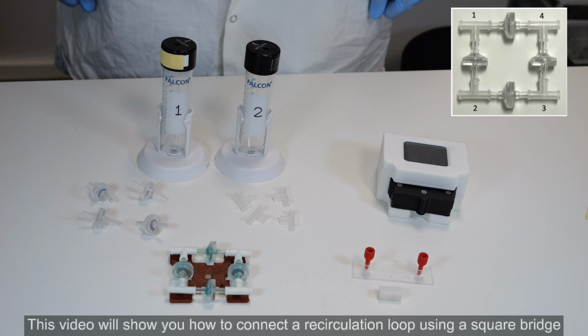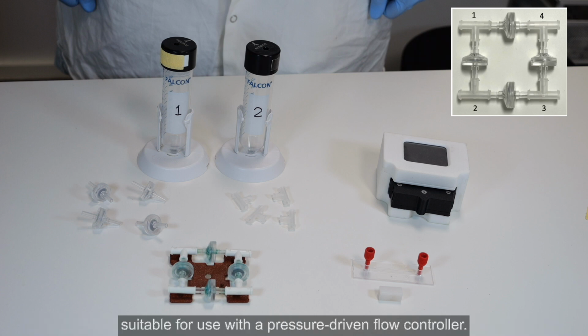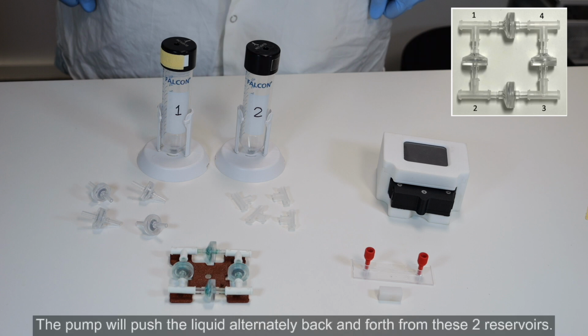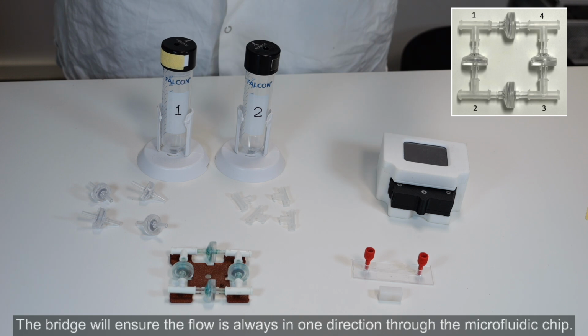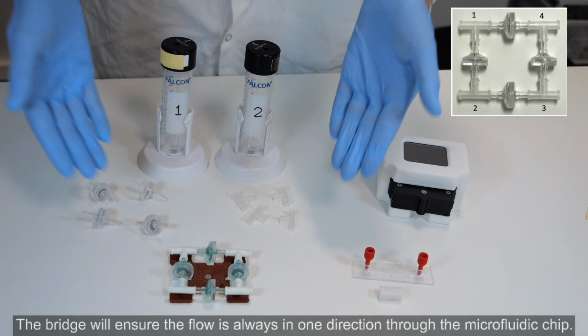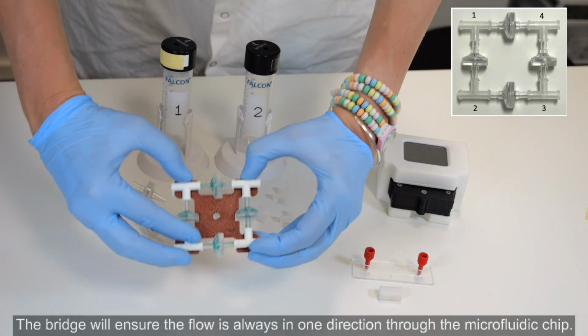This video will show you how to connect a recirculation loop using a square bridge, suitable for use with a pressure-driven flow controller. The pump will push liquid alternately back and forth from two reservoirs. The bridge ensures the flow is always in one direction through the microfluidic chip.